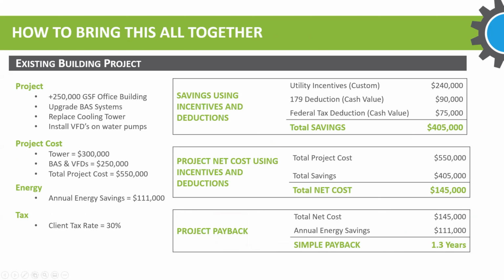So this is a project that we completed probably about 2 years ago. Existing building, office building, 250,000 square feet. The project was a small BAS upgrade. We talked with the owner, did some analysis, and did an energy audit to find out where their energy was being consumed and what improvements could be done. We expanded that initial project, which was really just going to be a BAS overlay, to installing VFDs, controlling the flow. It was a condenser loop with floor by floor SCUs and a cooling tower on the roof. So we replaced the cooling tower.